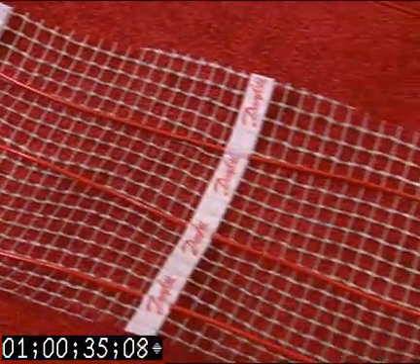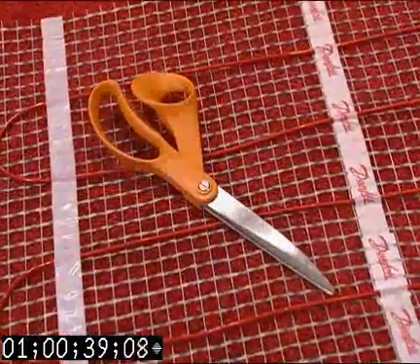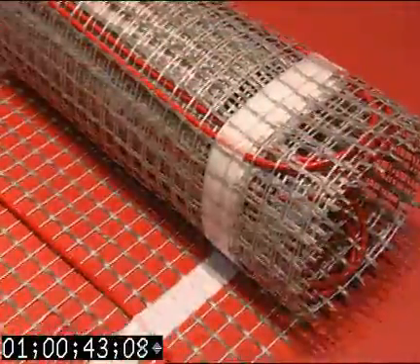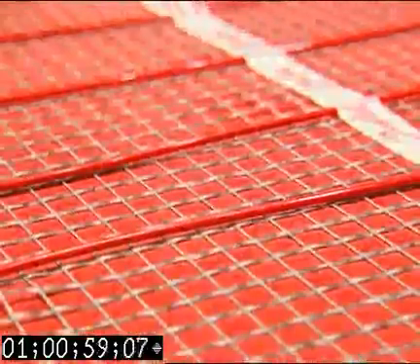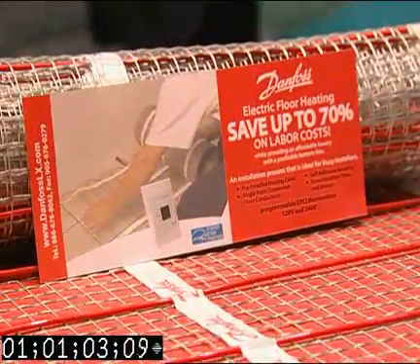The fiberglass mat can easily be cut to allow working around obstacles like toilets or sinks. The Danfoss LX mat is self-adhesive, which is unique in the industry. We take the heating cable and put it onto a mat, so the product goes down much quicker. We also eliminate the chances of errors because all of the cables are wound to exact specifications. The Danfoss LX self-adhesive heating mat can decrease installation time by 70%.